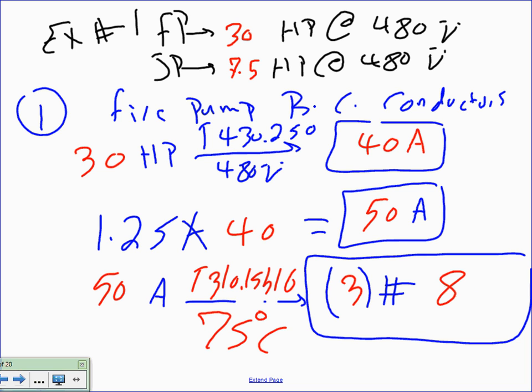RHW conductor. I know we could read up in the code, but what's the quick, fast way? You can use THHN. Well, RHW is rated for emergency feeders as an emergency feeder insulation. Typically you're going to find them... Yeah, it handles more heat, the insulation. Typically you put them in an EMT conduit. Like we said, all these feeders, guys, by code they have to be outside the building. They have to be buried in 2 inches of concrete, right? The feeders for the emergency system.